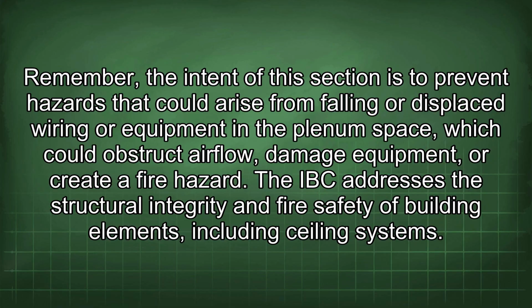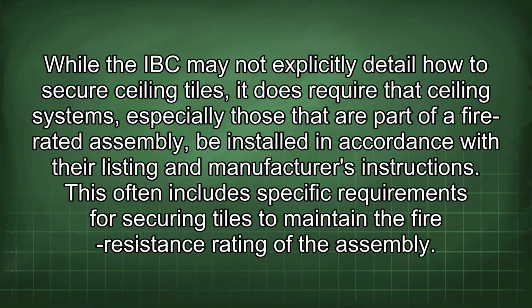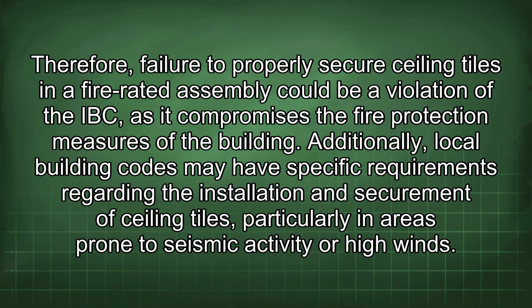The IBC addresses the structural integrity and fire safety of building elements, including ceiling systems. While the IBC may not explicitly detail how to secure ceiling tiles, it does require that ceiling systems, especially those that are part of a fire-rated assembly, be installed in accordance with their listing and manufacturer's instructions. This often includes specific requirements for securing tiles to maintain the fire resistance rating of the assembly. Therefore, failure to properly secure ceiling tiles in a fire-rated assembly could be a violation of the IBC, as it compromises the fire protection measures of the building.